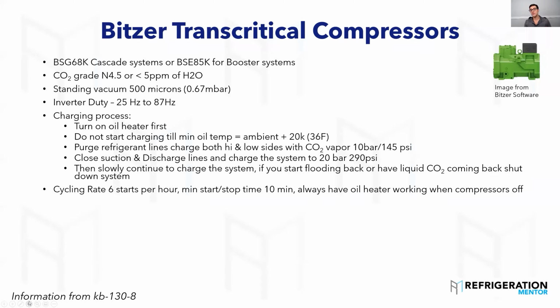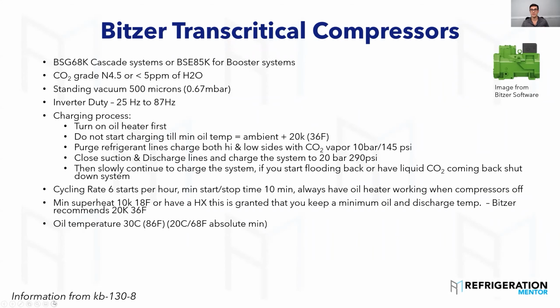Okay, they say in their manual that their cycling rate is 6 starts per hour. This is something you need to watch for. I've walked into many parallel rack rooms and I hear compressors banging on, banging off, banging on, banging off. They say 6 starts per hour in their manual, so the minimum start time is 10 minutes, like runs for 5 minutes, off for 5 minutes, that's 10 minutes, or whatever sequence that is. They also always want the oil heater on when the compressor's off. This is just a standard in our industry, but make sure you check that crankcase heater. I've seen it many, many times going in where 2 or 3 of them on a rack are not running. So you always want to check that oil heater, very important.